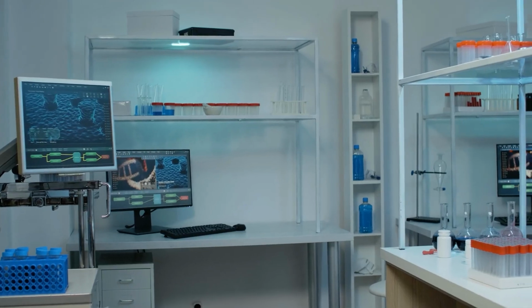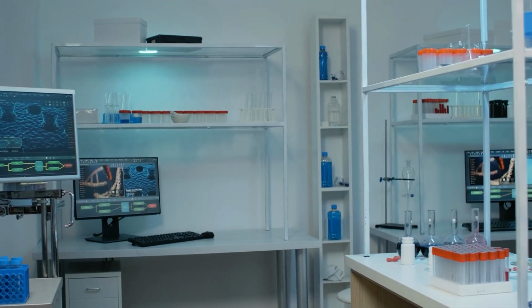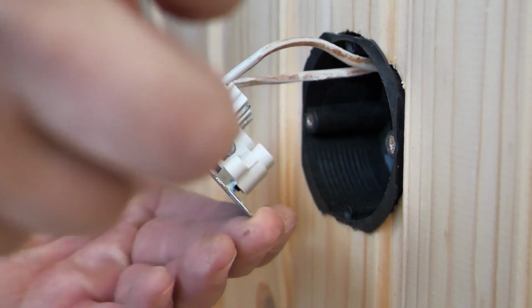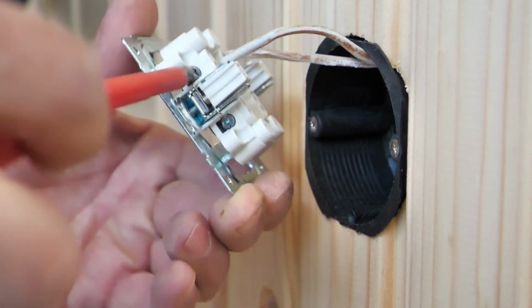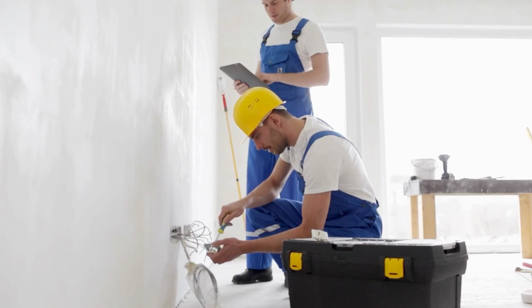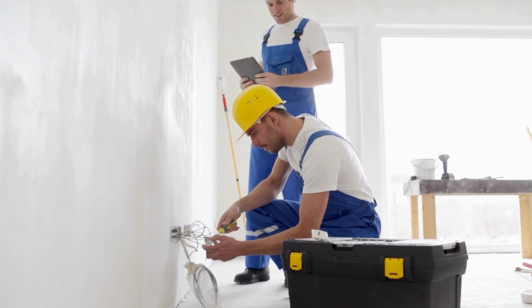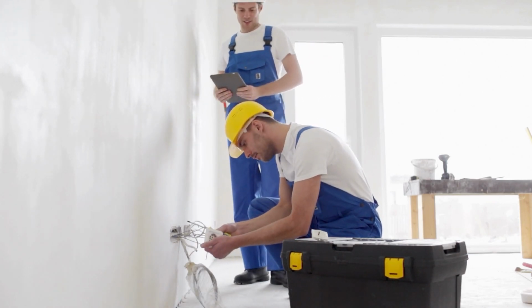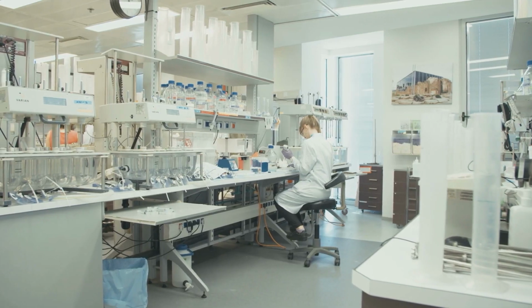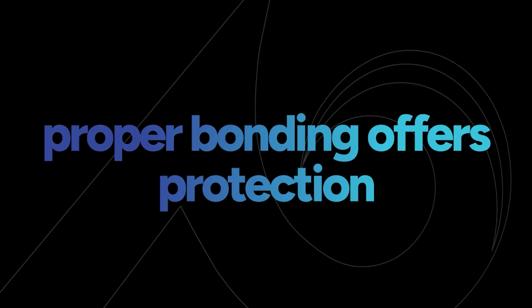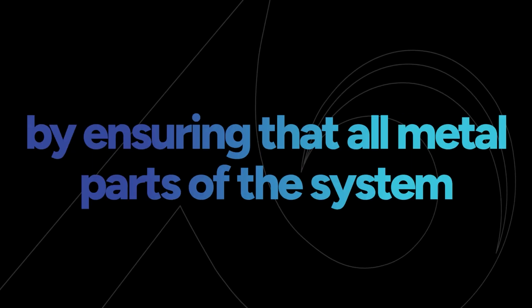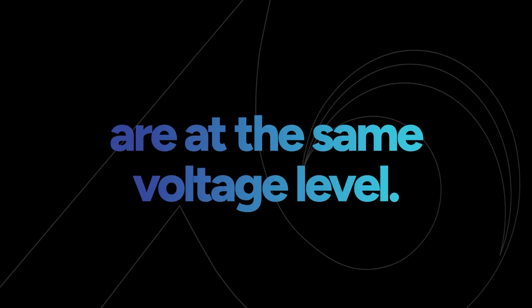However, there is something as important as setting the appropriate electrical layout. It involves proper grounding and bonding of electrical systems to avoid the risk of electrical hazards. This ensures that in case of a fault, the electrical current has a safe path to the ground, reducing the risk of electric shock and equipment damage. Meanwhile, proper bonding offers protection by ensuring that all metal parts of the system are at the same voltage level.